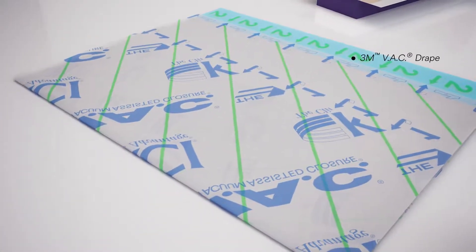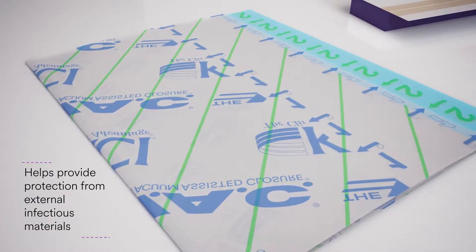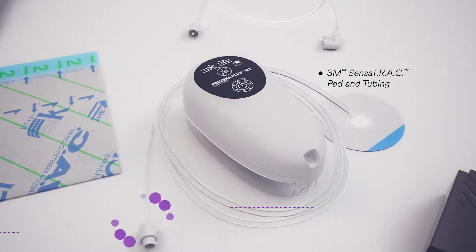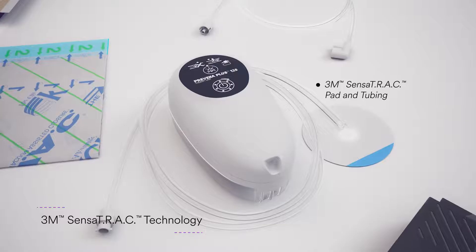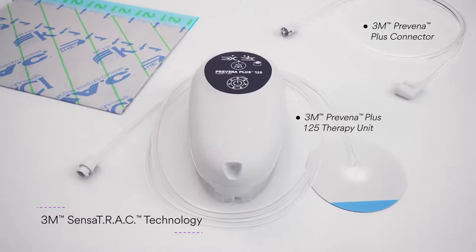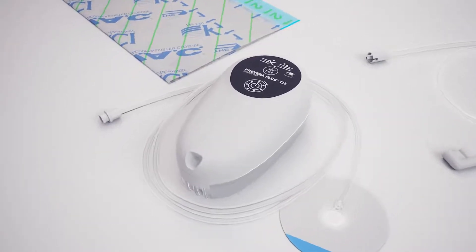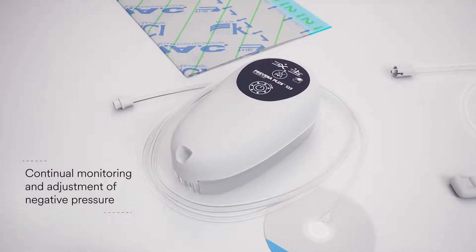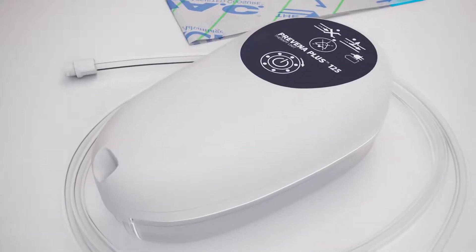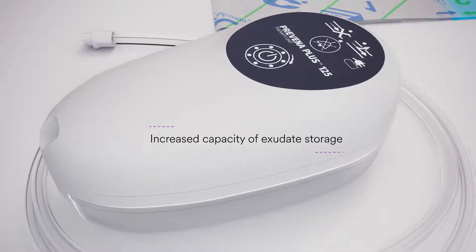The 3M Vac Drape covers the foam dressing and adheres to the skin, providing protection from external infectious materials. In addition, the 3M Sensatrac pad and tubing, utilizing 3M Sensatrac technology, connects directly to the 3M Prevena Plus 125 therapy unit via the 3M Prevena Plus connector, without the need for a 3M Prevena therapy vac connector. Sensatrac technology provides continual monitoring and adjustment of negative pressure at the incision site. The 3M Prevena Plus 150 mL canister allows for increased capacity of exudate storage.